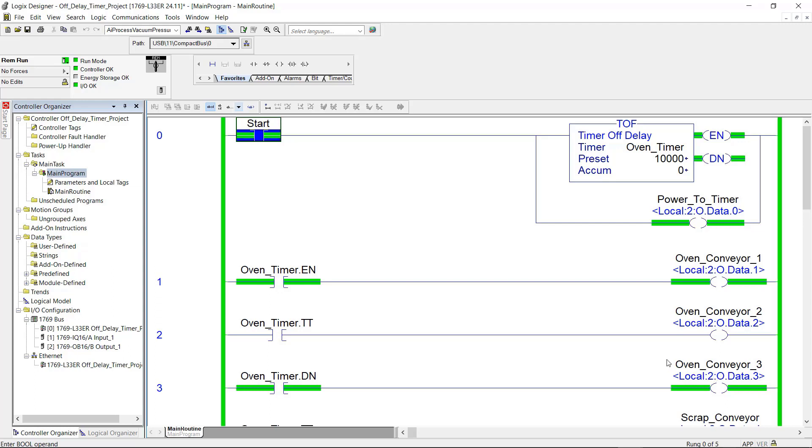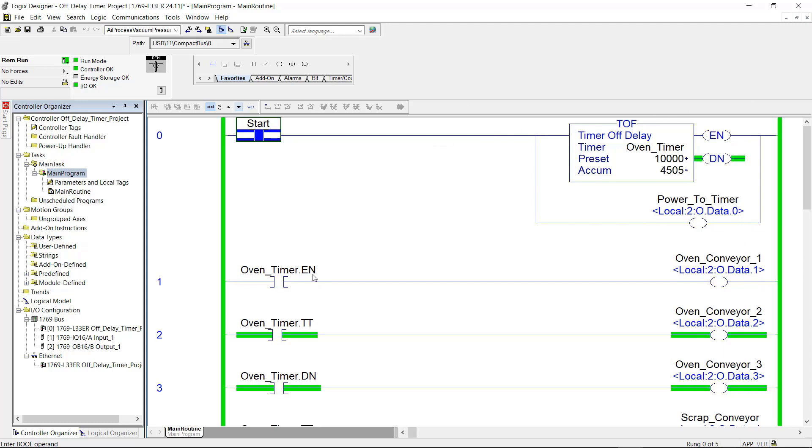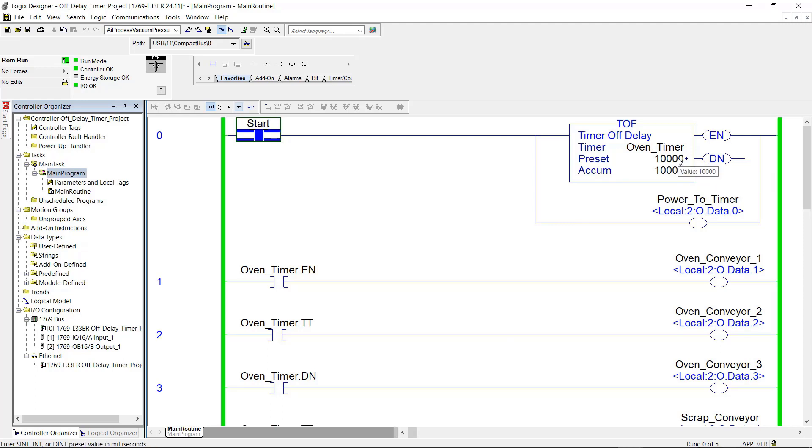Now if I cycle this, you're going to see the timer will start the time. The enable bit will turn off. The time timing and the done bit will both be true. Now here we go. Now the timer is timing. The enable bit is false. My power to the timer output is also false. Now everything is false because the timer has accumulated to the preset.